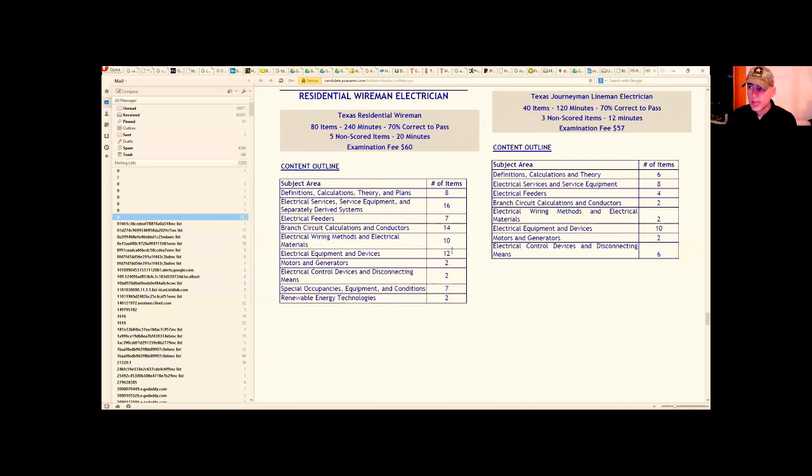Yes. It's a really important table for you, but the first thing to kind of get this stuff rolling is I put the word Romex across the top of the 60-degree column. Where it says 60 degrees, just right above that 60-degree C, just put Romex. Put motors across 75 degrees. Yeah, just put the word motors across the top of 75. And then the 90-degree column, above the top of that, put, well, there's a couple things you can put on there, but put the word derate only.